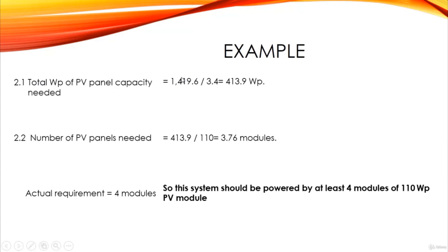Now let's apply this to our example. From step one, the total watt hours is 1419.6. To get the total watt peak capacity, we divide this by the panel generation factor of 3.43, giving us 413.9 Wp for our system. We are using a 110 watt peak module, so we divide 413.9 by 110, which gives us 3.76 modules.